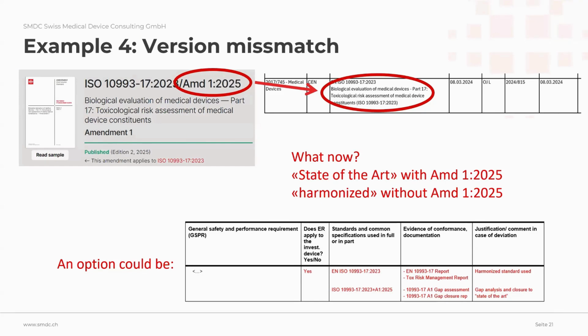The only thing that I can say about what you just said is that sometimes it's the battle between the intent of the regulation or a directive and the opinion of somebody at the notified body, and getting these two reconciled sometimes is a problem. It requires a great ability to put the technical aspect in place in a way that it's not debatable, and that's really the problem. You have to go back to the black and white and call them out on that: please show me in the regulation where it states what you are telling me it has to be. Exactly. You have to ask them to show it to you in the regulation, and that's how you win that battle. A lot of times they can't show it to you.